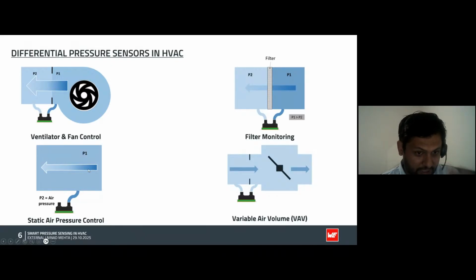Another example is static air pressure control. Here you use the differential pressure in a sort of gauge configuration, where one port is always open to the air and another port always monitors the pressure of the air vents. These kinds of applications are also very common in clean rooms or in hospitals, where in ICUs or operation theaters, the air pressure inside these rooms needs to be different from the lobby so that the contamination doesn't go in.